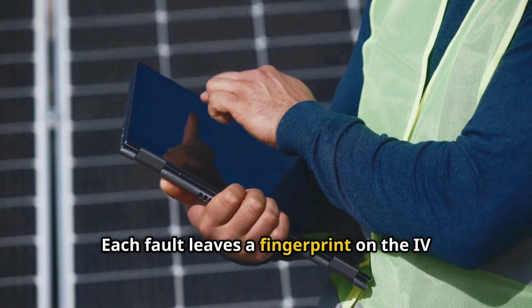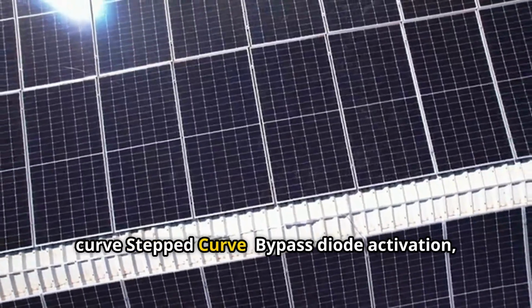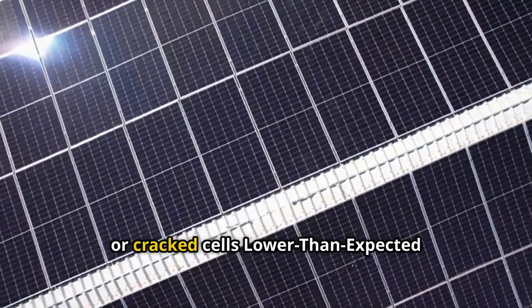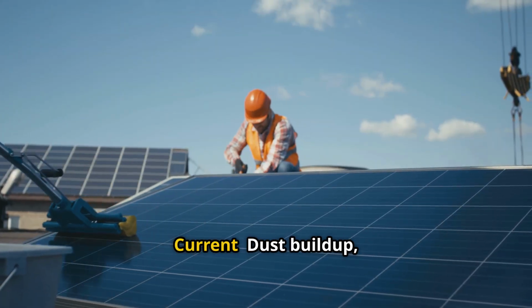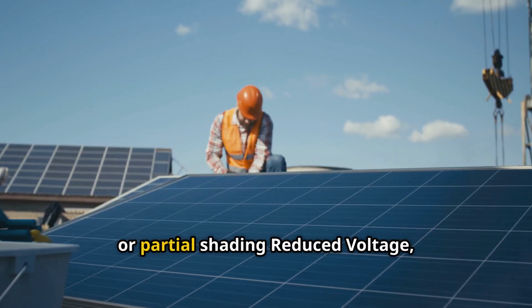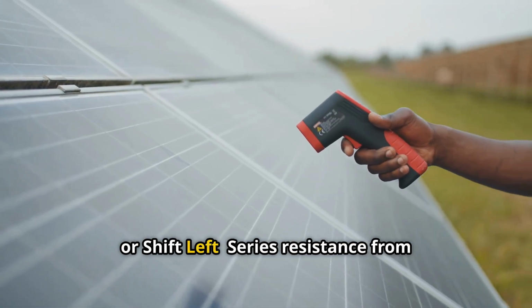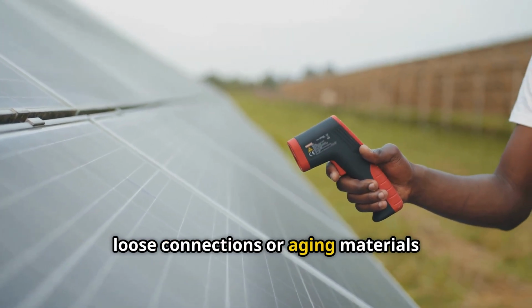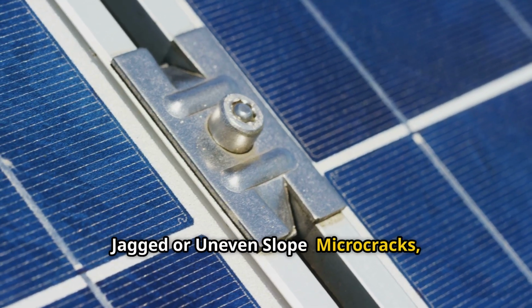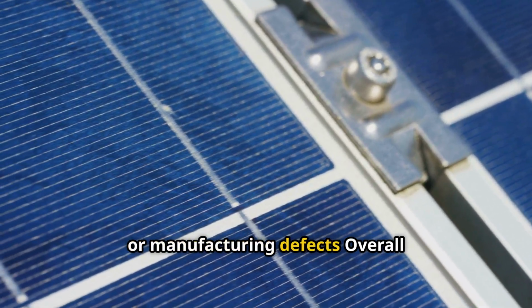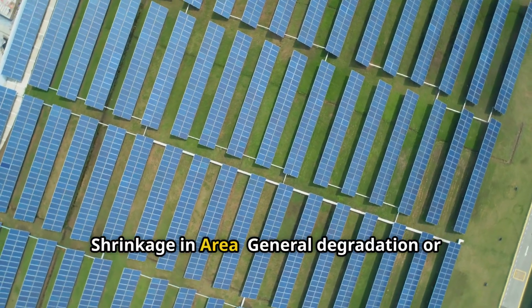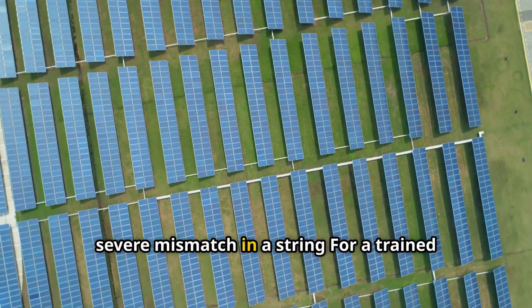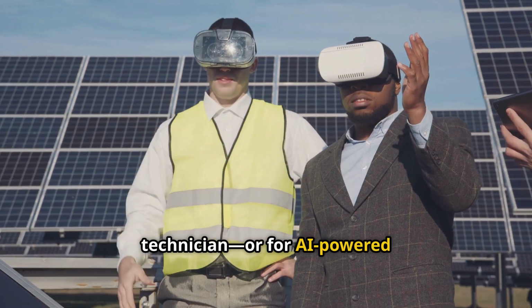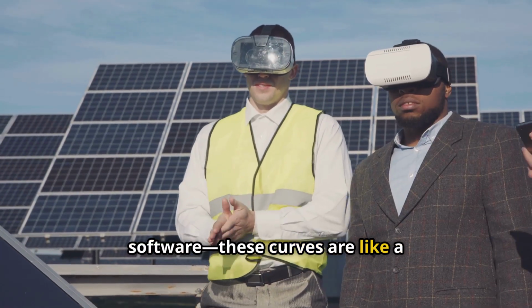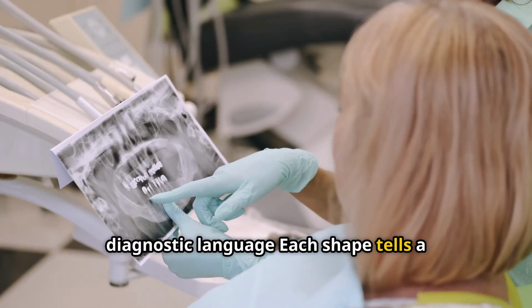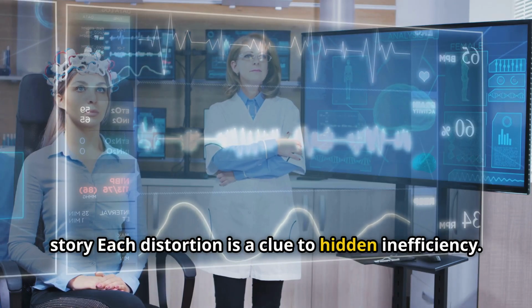Each fault leaves a fingerprint on the IV curve. Stepped curve: bypass diode activation, shading, or cracked cells. Lower than expected current: dust buildup, bird droppings, or partial shading. Reduced voltage, or shift left: series resistance from loose connections or aging materials. Jagged or uneven slope: microcracks, hotspots, or manufacturing defects. Overall shrinkage in area: general degradation or severe mismatch in a string. For a trained technician, or for AI-powered software, these curves are like a diagnostic language. Each shape tells a story. Each distortion is a clue to hidden inefficiency.